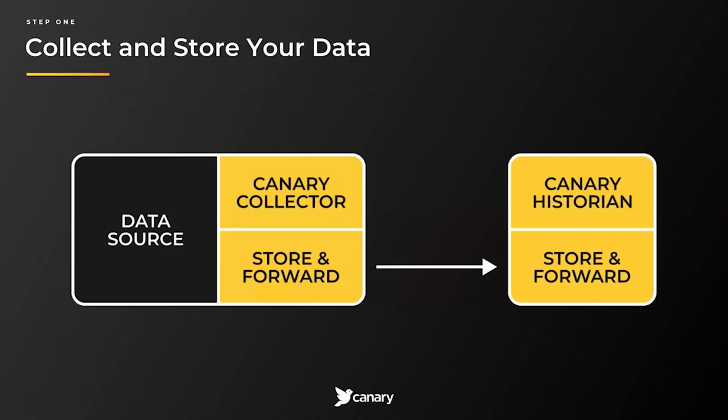Now let's talk a little bit about our store and forward technology. Never worry about losing your data again with Canary's Store and Forward. By installing the Canary Collector local to the data source, you can leverage our Store and Forward technology. It provides buffering of data. It provides HA at both the data collector and the historian levels. You can send data to multiple site-level historians or a site-level historian and corporate-level historian at the same exact time. And now you could send data to a local historian and a corporate historian without adding complexity.